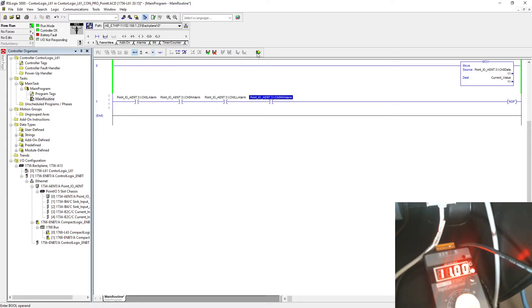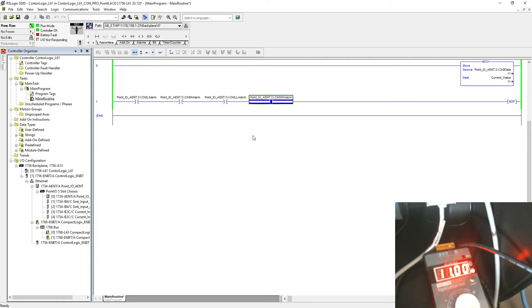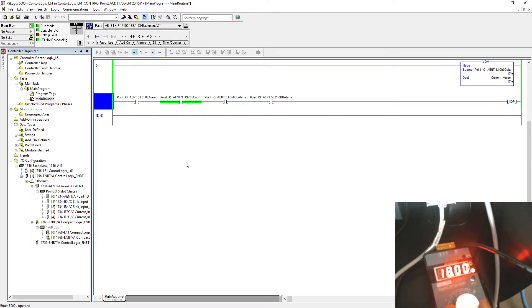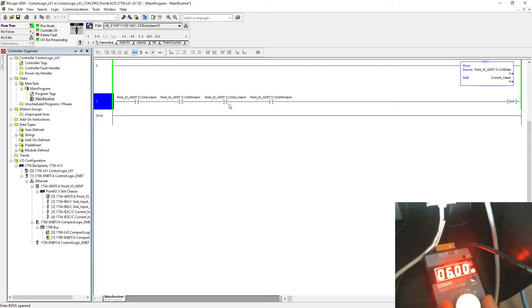So everything we have visibility from our program now. Let's see if I'm going above 16. There you go, my high alarm turns on. When I'm going above 18, my high-high alarm turns on. When I'm going under 4, my low alarm turns on. Under 2, my low-low alarm turns on.